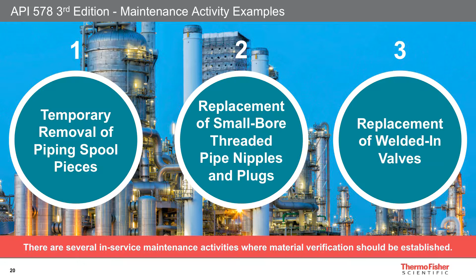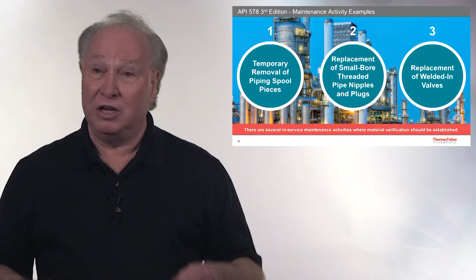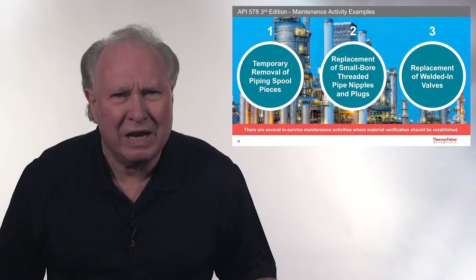In these maintenance activities, one thing is the temporary removal of a spool piece. You've got to tag it, mark it, and do PMI. There's an example of a spool piece put in the wrong location - it was carbon steel when it should have had chrome moly in it, and it exploded and blew up. Didn't even last 3,000 hours, man. That's no time at all.